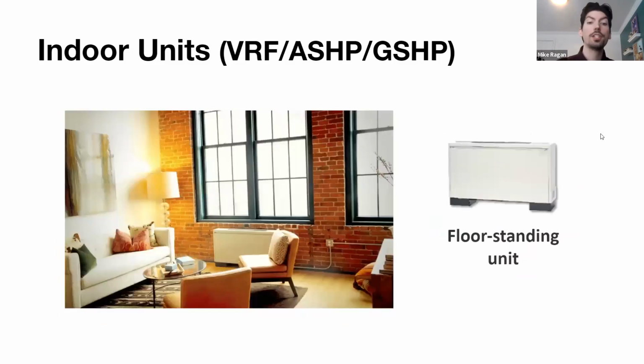We have floor standing units. These are great swap outs for any existing radiators that may exist in the space. These are available in both an exposed and a concealed setting. The exposed here is just showing it has an aesthetic plastic exterior, but we also have one that could be built into a wall or built into millwork potentially. We see that actually oftentimes in churches. So right underneath where the stained glass windows would be, built into the wooden millwork on the sides, we would build in these floor standing units to blow heat up from the sides.